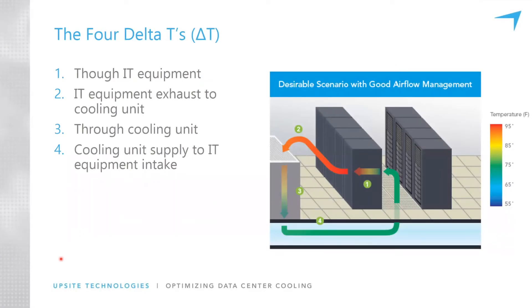Another very valuable way to understand cooling optimization is to look at the four delta T's in the room. There are four delta T's in the airflow path as it moves through a room. IT people are focused on the temperature change as air moves through the IT equipment; mechanical people focus on how much air temperature drops through the cooling units. But there are two other delta T's: how much air heats up from leaving a cooling unit before reaching the warmest intake, and how much air cools off from leaving IT equipment exhaust before returning to a cooling unit.